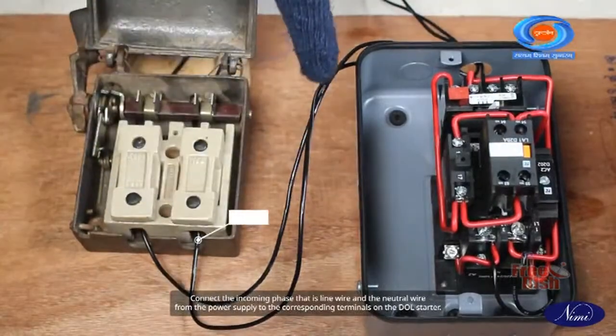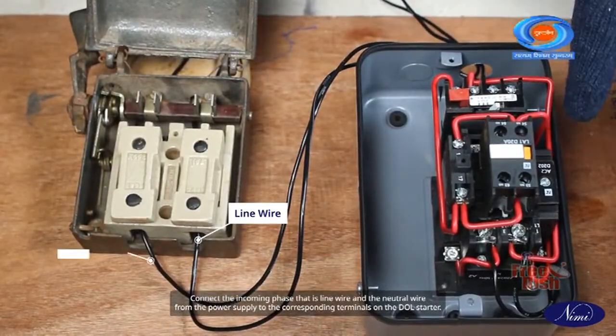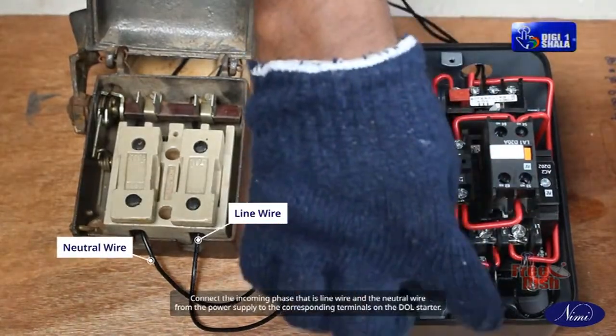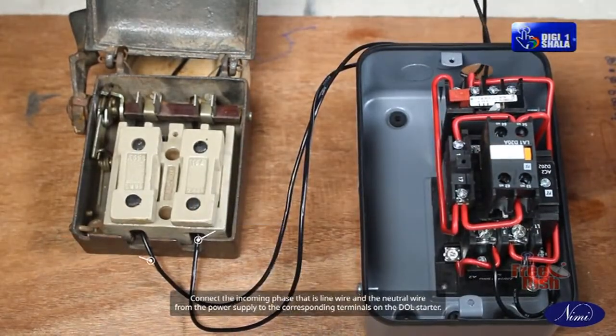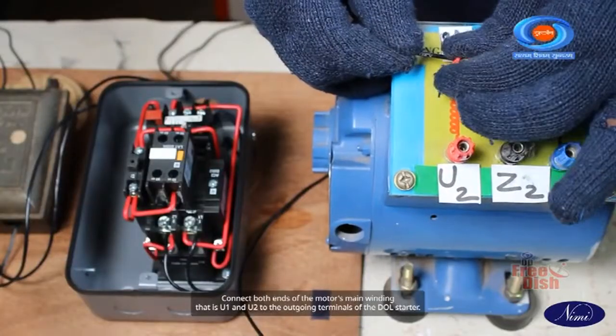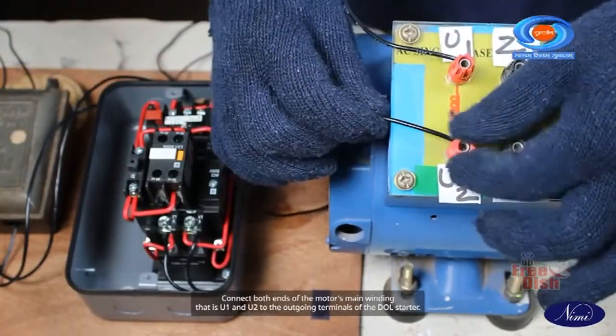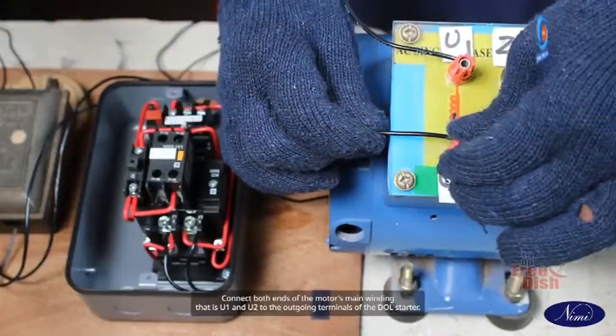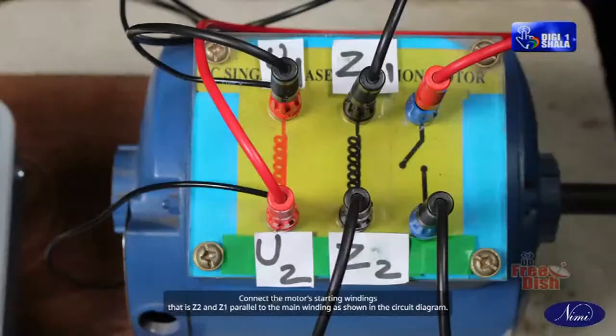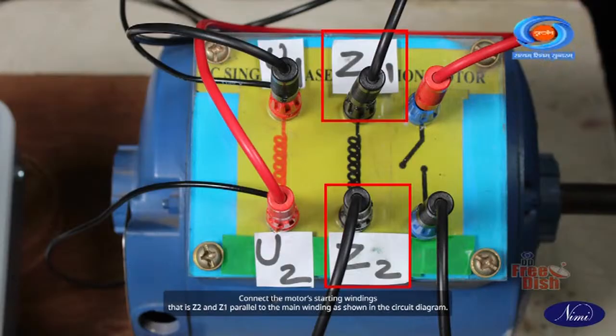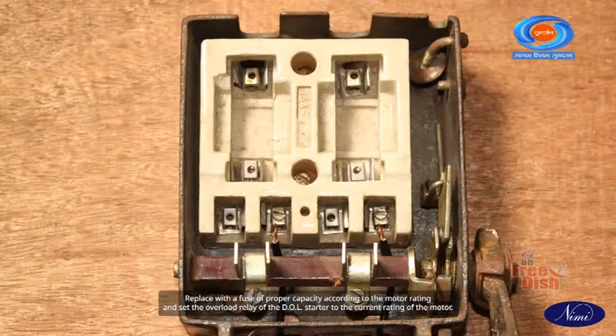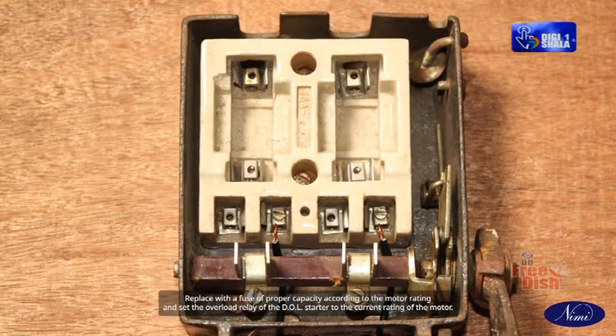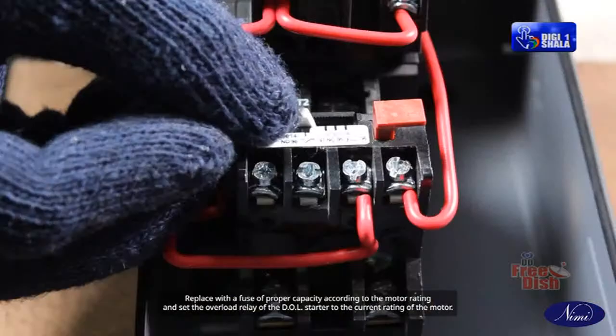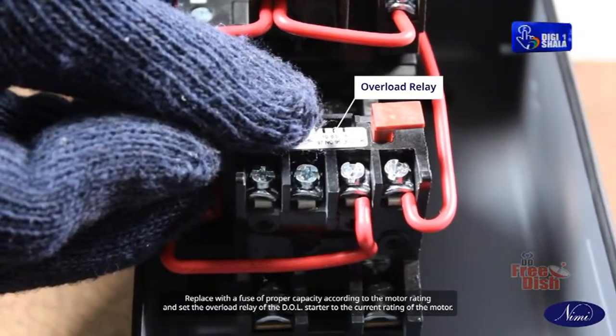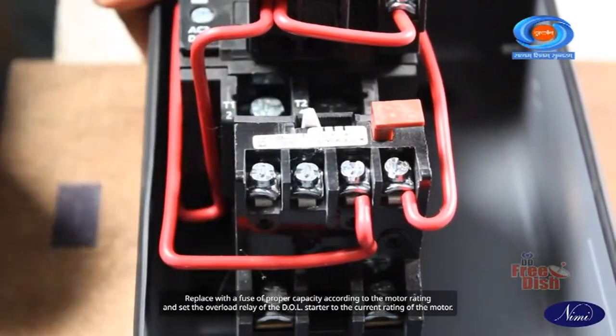Connect the incoming phase, that is the line wire, and the neutral wire from the power supply to the corresponding terminals on the DOL starter. Connect both ends of the motor's main winding, that is U1 and U2, to the outgoing terminals of the DOL starter. Connect the motor's starting winding, that is Z2 and Z1, parallel to the main winding as shown in the circuit diagram. Replace with a fuse of proper capacity according to the motor rating and set the overload relay of the DOL starter to the current rating of the motor.